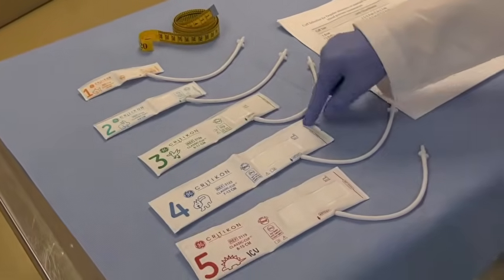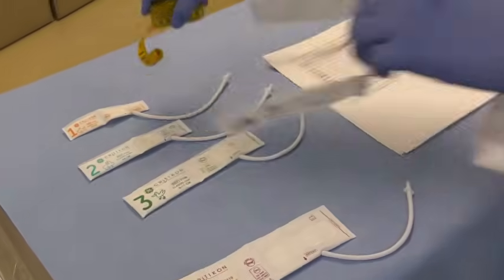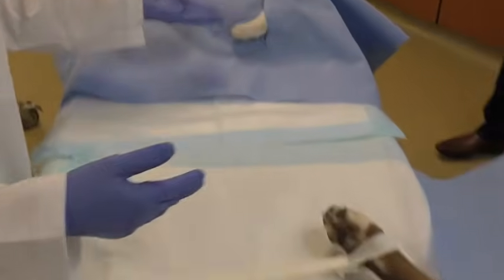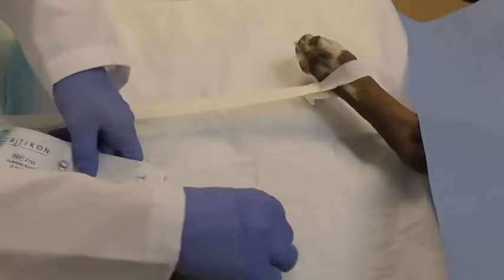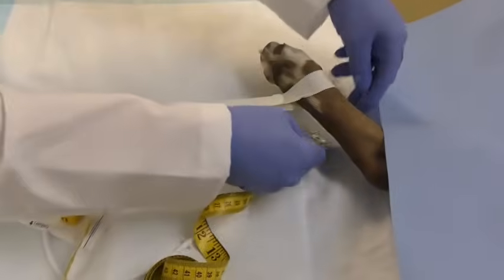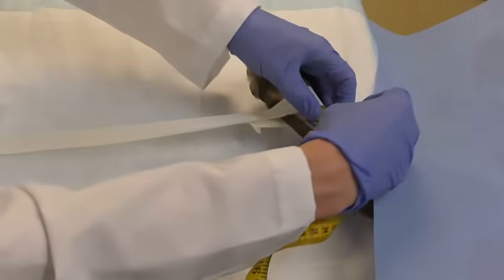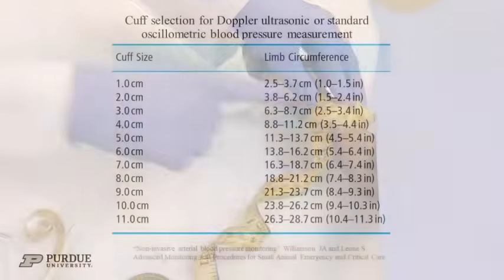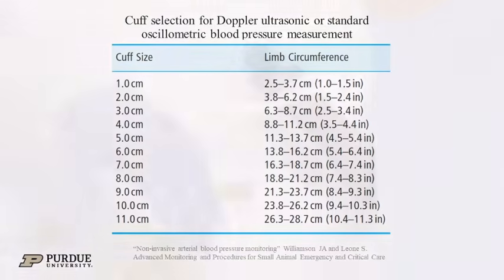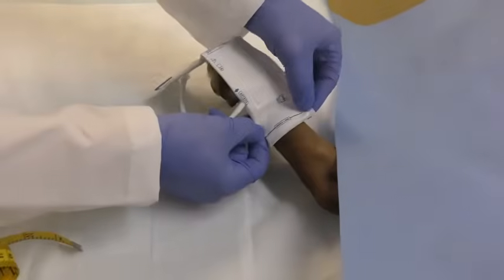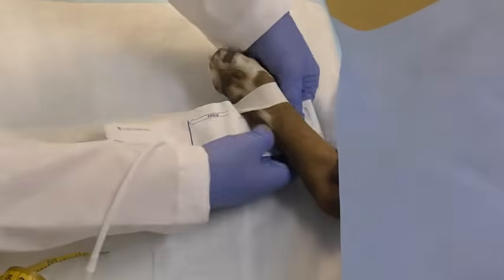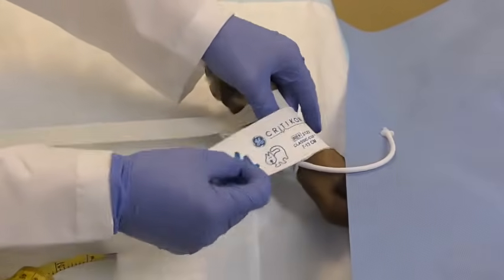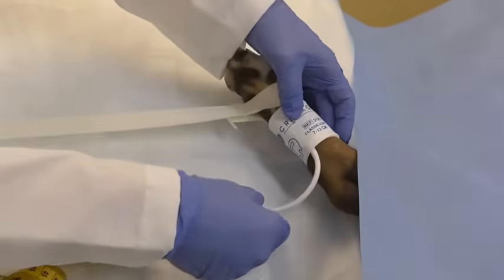First, the width of the cuff should be 40% of the circumference of the limb in dogs, and 30 to 40% of the circumference of the limb in cats. Ideally, the circumference is measured at the site where the cuff will be placed, and compared to a chart which shows appropriate cuff sizing based on the circumference of the limb. Alternatively, the index line can be held up to the limb to visually estimate whether it covers less than 40% of the limb circumference. A cuff that is too small will falsely elevate the non-invasive blood pressure reading, and a cuff that is too large will falsely decrease the reading.